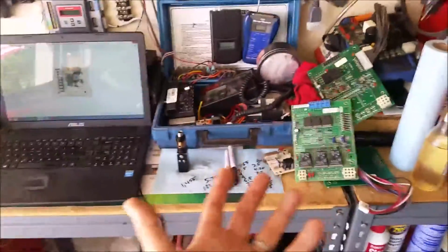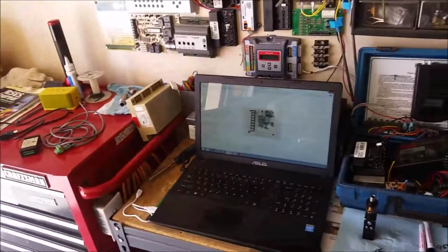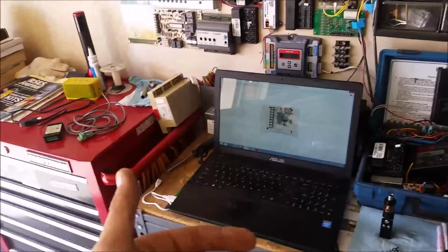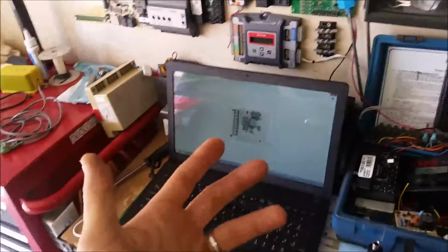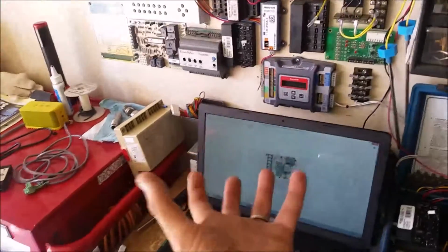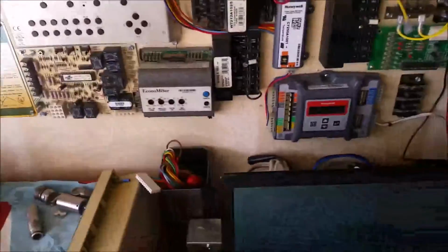The newer versions, the larger versions where it's built into the board, basically if something tripped, it was your job to figure out what it was. It didn't tell you what it was. So you'd sometimes spend 10, 20 hours aggravated, returning day after day, looking for nuisance trips. And York decided to do something. They decided to create what they called the Simplify, to take this board, simplify it, and make one board to rule them all. And that's what they decided to call the Simplicity board.